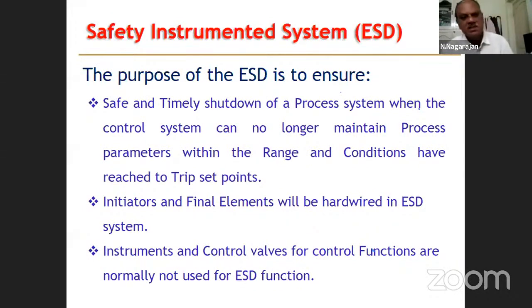And how this works, safe and timely shutdown of a process system when the control system can no longer maintain the process parameters. When the control system fails and the variables are going out of control, then they lead to a process upset, which may lead to a hazardous situation, and incidents or accidents may happen. In such a situation, ESD system comes into the picture and it will try to control and contain the hazards. So it will go to the trip mode. It will go to the shutdown of the system or equipment or the plant.